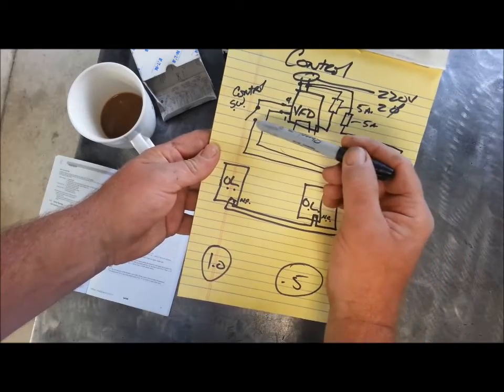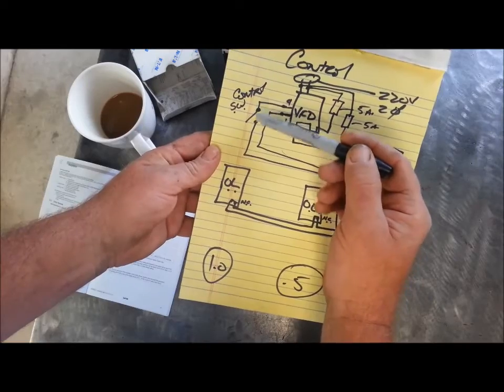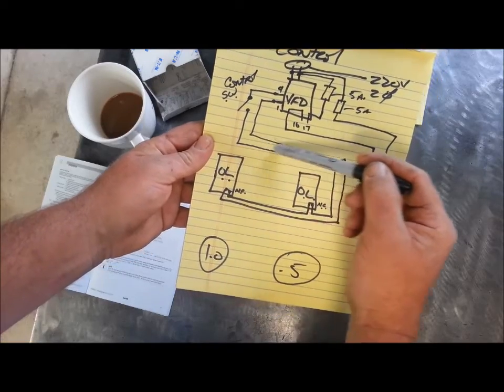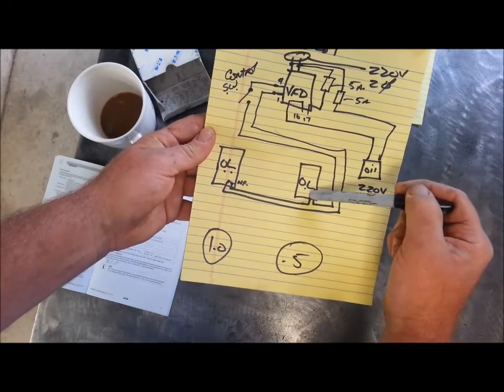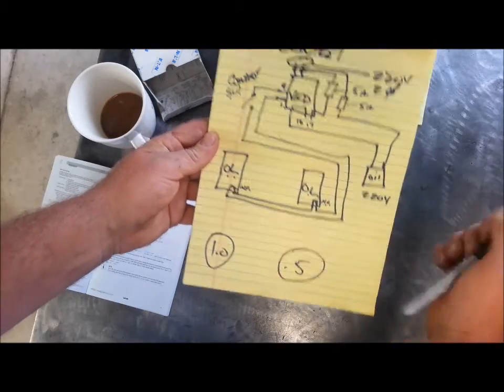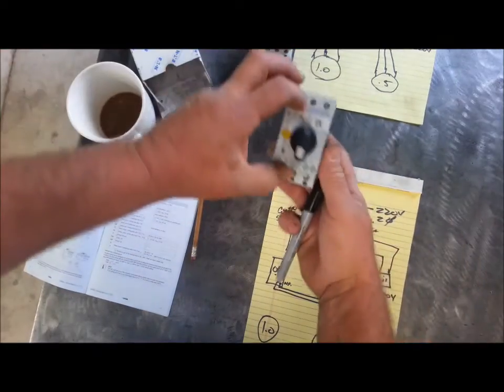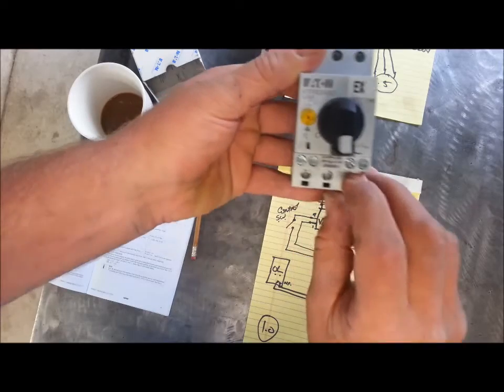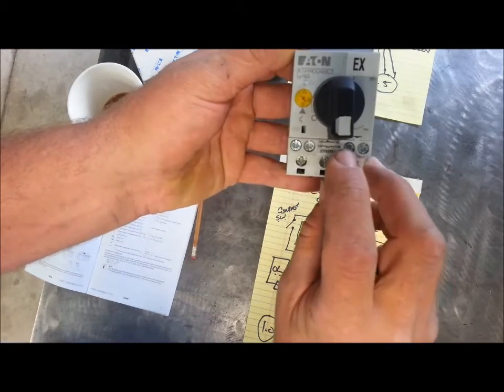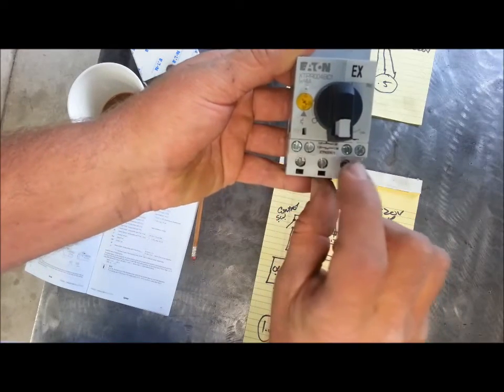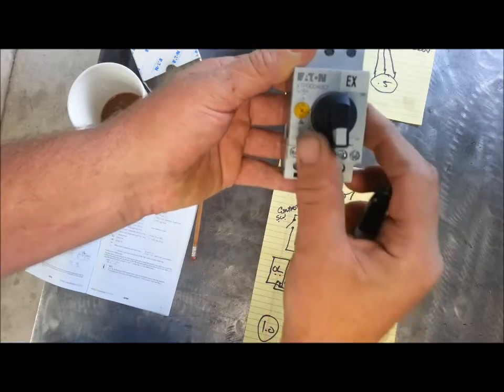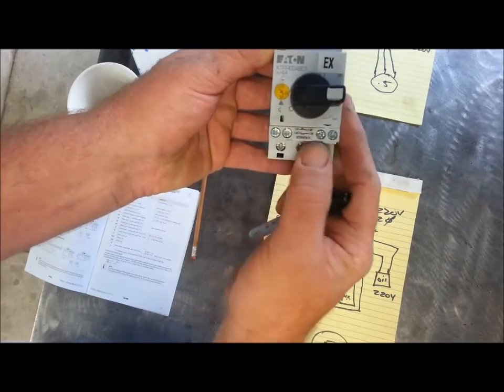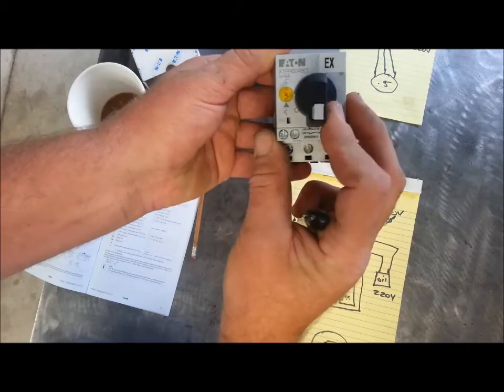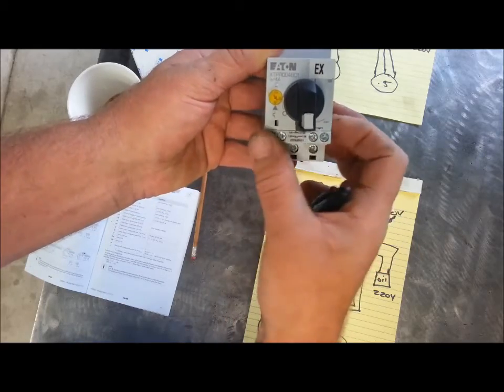Control switch there, maintain contact, and then come down, and you want to go through your auxiliaries on your overload blocks. And these are these small terminals here and here. It's got a normally open side and a normally closed side, but we want the normally closed. So when this thing trips, that switch opens. And these are just pilot duty. You're not running any big power through there.